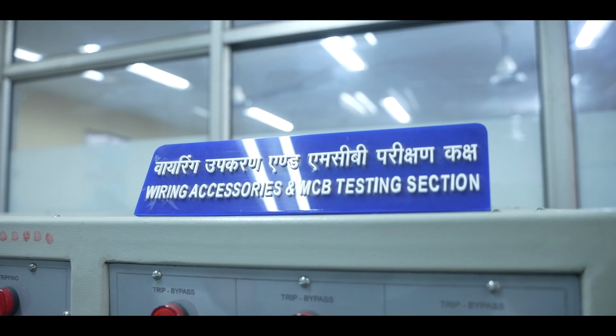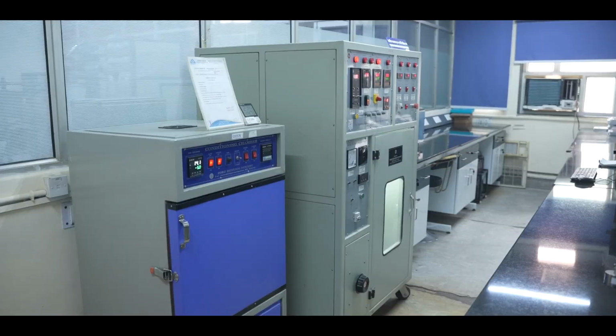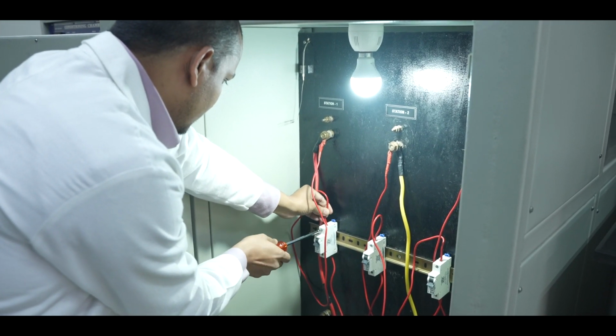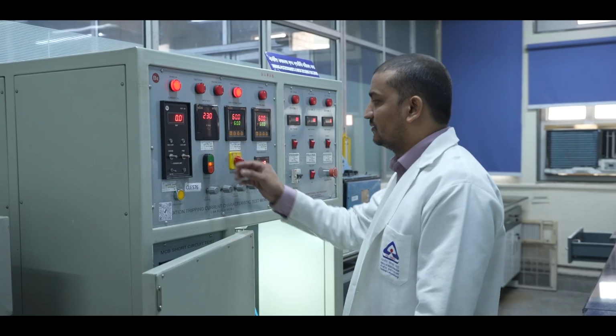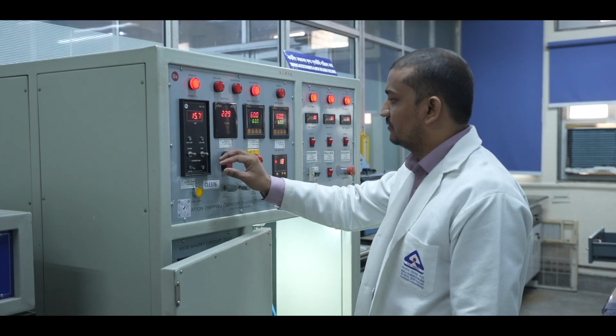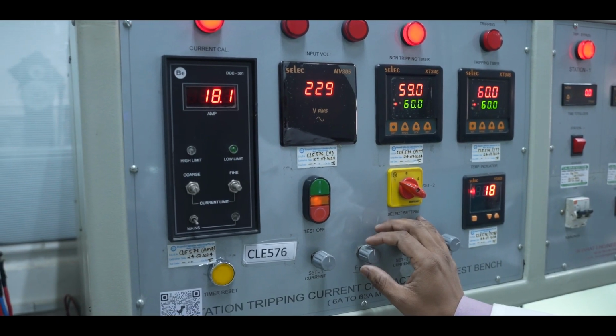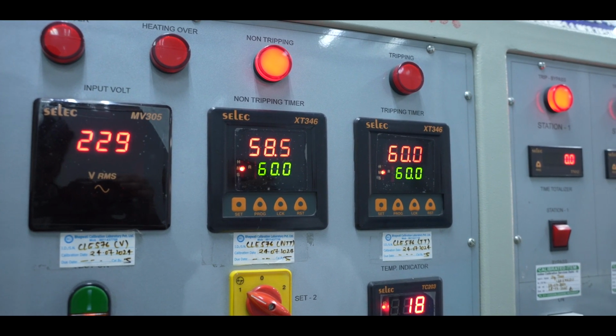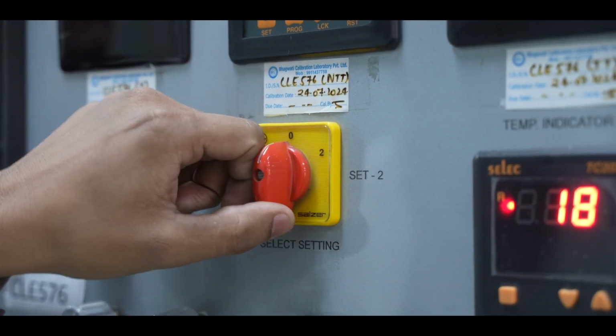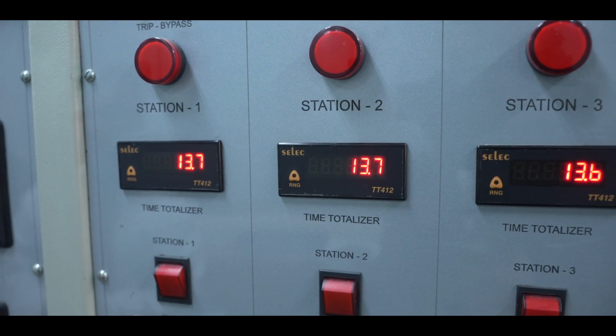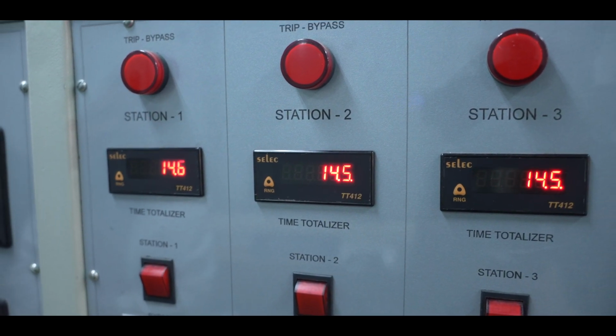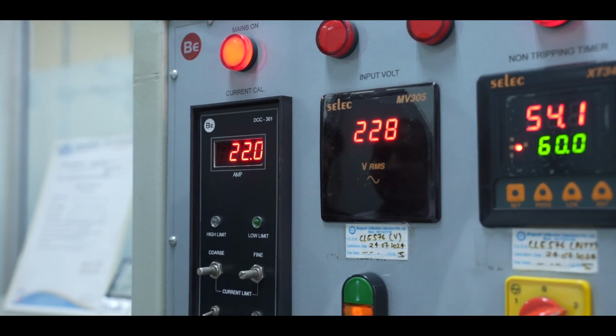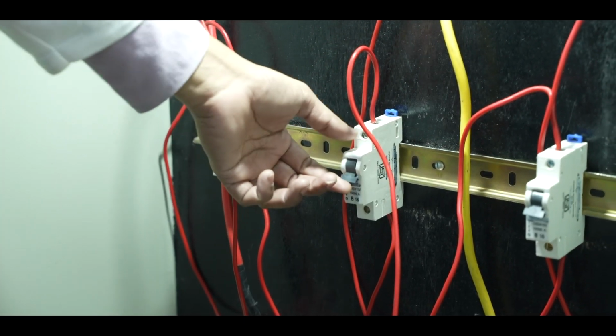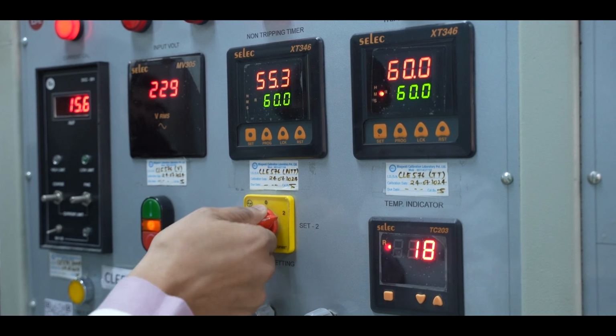Tripping test. The tripping test of MCBs as per IS 60898 ensures their reliability under overload and short circuit conditions. In the overload test, a current of 1.13 times the rated current is applied for 1 hour for MCBs up to 63A and 2 hours for those above 63A, during which the MCB must not trip. Next, the current is increased to 1.45 times the rated current, where the MCB must trip within the same respective time limits.